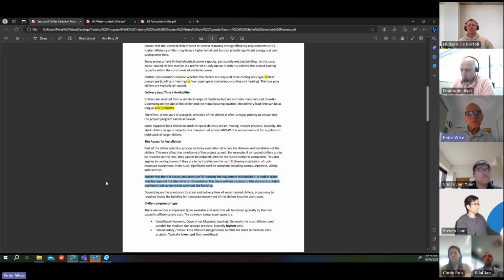Ensure that there's access and provision for hoisting the equipment into position. And sometimes, a new building will have a site crane, which may or may not be available when the chillers have to be installed. And I know builders generally want to get the tower cranes off the project as soon as they can because they cost money. And so if you're not ready to get the chillers up there as soon as the roof is ready, they might pull the crane down. I've seen this happen too. So I'm just giving you a few little things to be careful of. Make sure that everything's ready. If they take the tower crane down, you'll need a mobile crane.